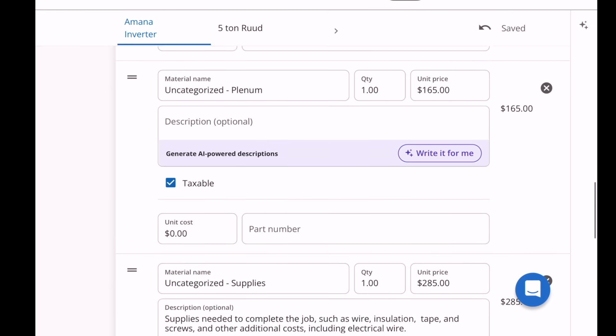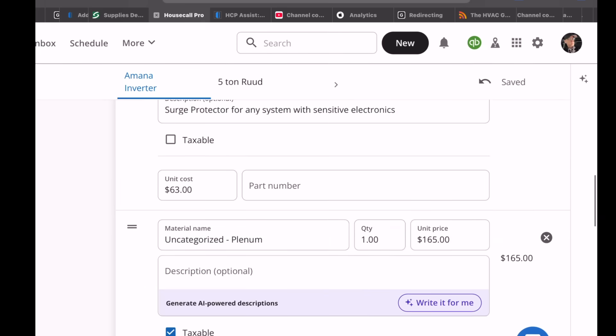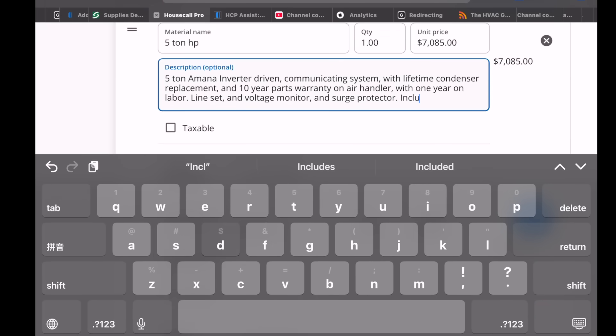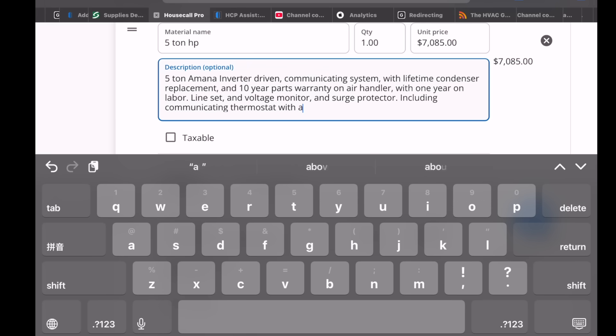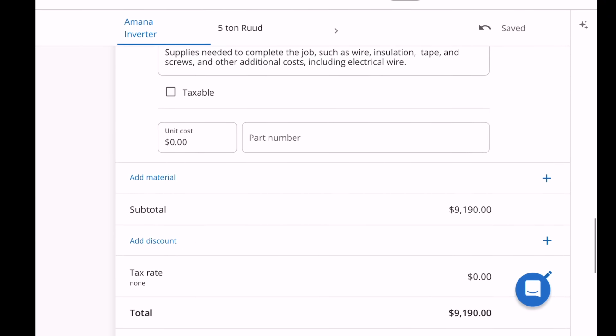So I've got a float switch, a surge protector, a plenum, and some supplies. The system includes a communicating thermostat that can help control humidity. The customer opted for no heat strips on this one - they don't need heat strips until you get down to negative 40 degrees, and here it never gets below about 17 degrees. I did explain to him that you might want them in case the condenser fails, but he has two other systems in the house for downstairs. That's my basic price: $9,190 with no markup.